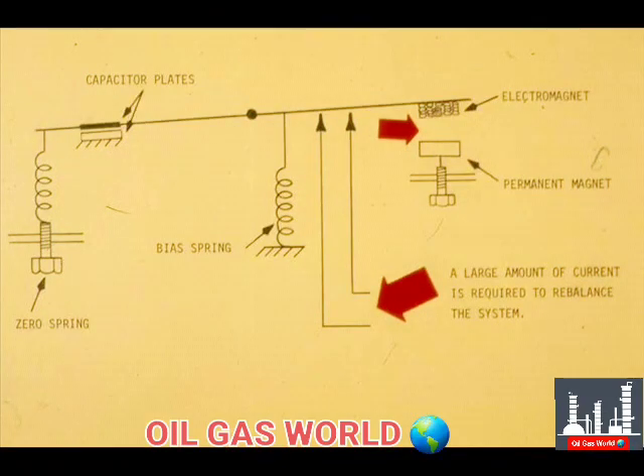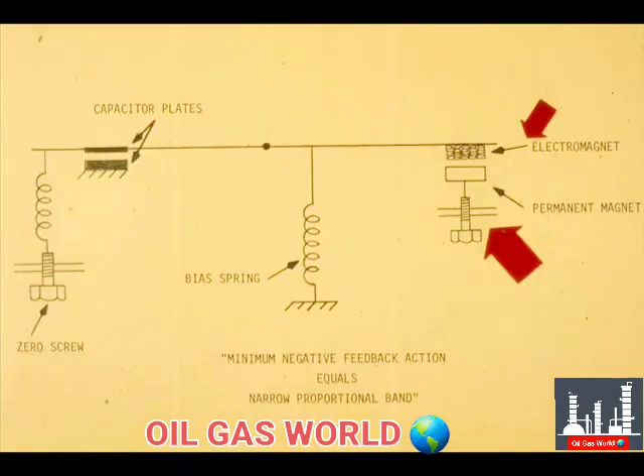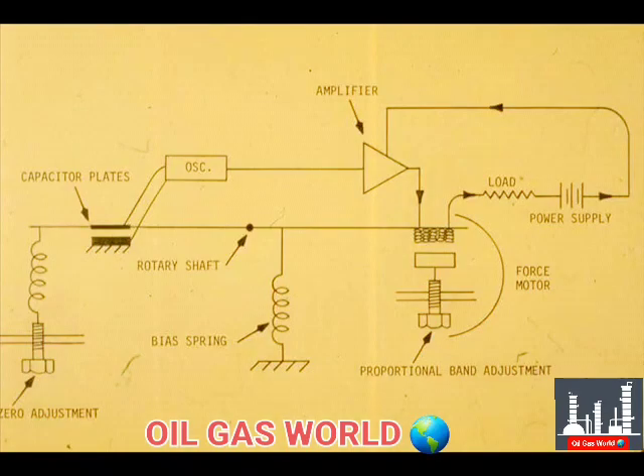When the permanent magnet is farther away from the electromagnet, the force motor is weaker, so it takes more current to produce the necessary rebalancing force. When the permanent magnet is farther away, the proportional band is narrow because negative feedback action is minimum. For a given movement of the capacitor plates, it would take a great amount of current to produce the necessary negative feedback. Here is our completed schematic. Study the components and adjustments for a moment.